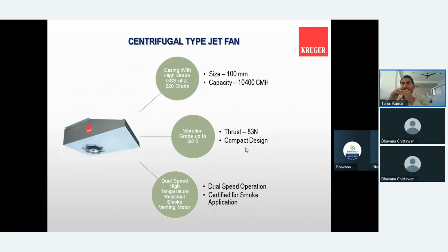Now feature-wise: in the axial jet fan there is a sound attenuator, whereas in the centrifugal fan there is no sound attenuator, since it works on the concept of a centrifugal backward curve impeller, whereas the axial jet fan works on the axial concept. The main feature of the centrifugal jet fan is this: if you are using an axial jet fan, the attenuator has certain acoustic properties, and suppose today you are getting 80 dBA. After 5 years you will not get the same 80 dBA, because dust and moisture particles will accumulate in the attenuator and the acoustic property of the attenuator will go off. Whereas in a centrifugal fan there is no such concept. This fan runs at 725 RPM, which is quite low, and the highest RPM for this centrifugal jet fan is 1450.